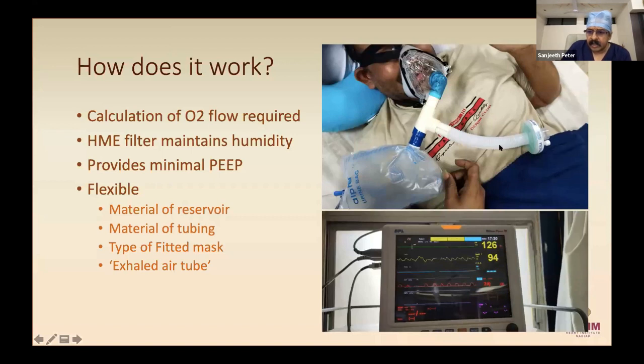This circuit, in addition, provides a minimal PEEP. As you can see, we tried measuring the amount of PEEP. At the end of the circuit, all the filters have a Luer lock, and you connect the Luer lock to a device which measures the pressure generated within. We found that it actually produces a small amount of PEEP, only about 2, but that seems to be enough.